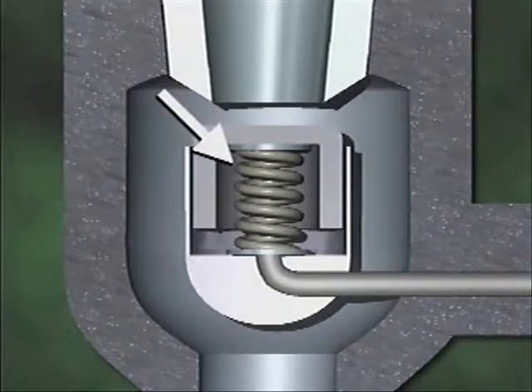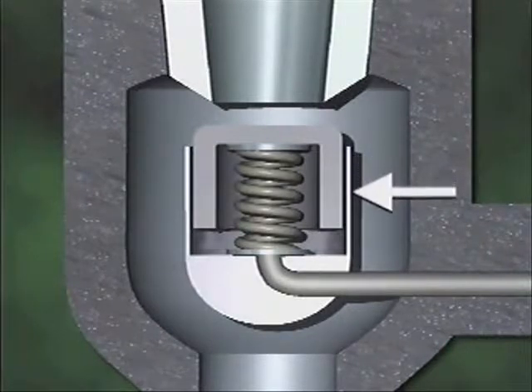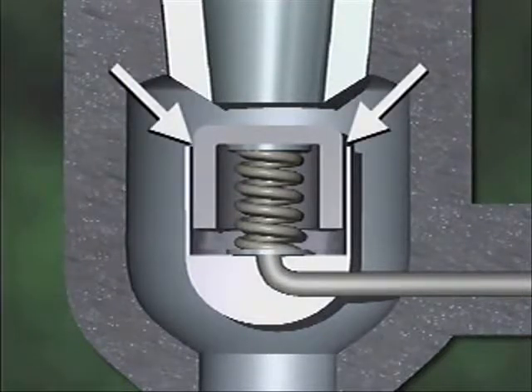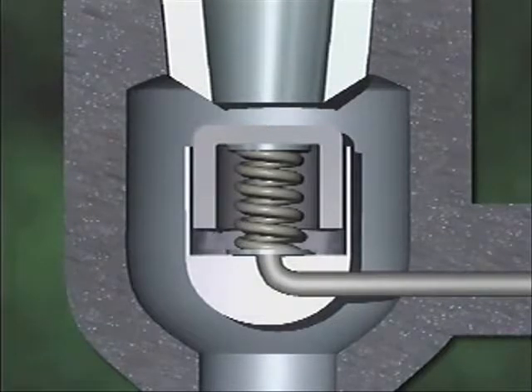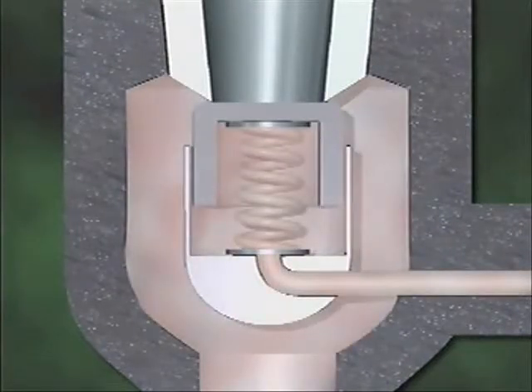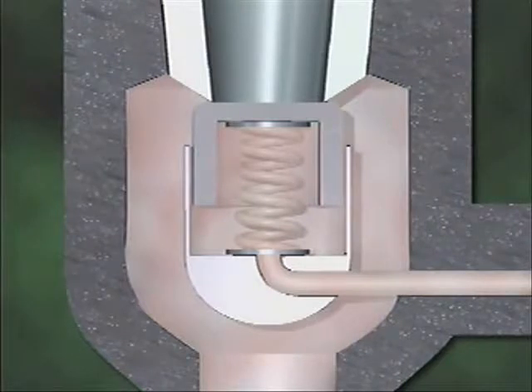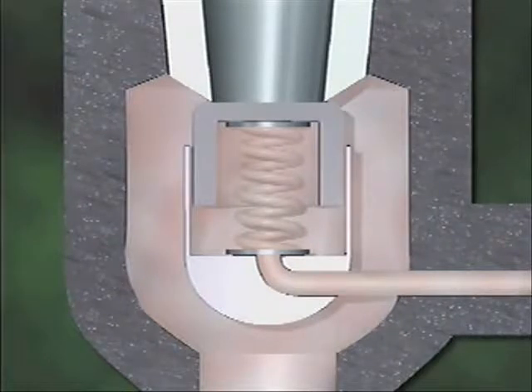The valve also has a disc guide, which is a sleeve that aligns the disc with the seat. A small opening between the disc guide and the disc allows system fluid to pass through from the inlet to the bottom of the main disc. Consequently, system pressure is exerted on both the top and the bottom of the disc during normal operation. Spring tension is also exerted on the bottom of the disc. If system pressure increases, it increases on both sides of the disc, but the valve won't open because the pressure on top counterbalances the pressure on the bottom, and spring tension holds the valve closed.